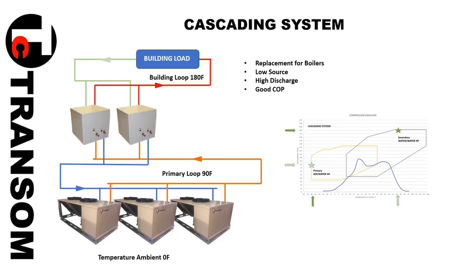Have you experimented with split systems that make it possible to get rid of the heat exchanger and the heat transfer fluid that's antifreeze in your primary loop? Yes, I've done that before. And if it was ground source, you could do it. But with air source, it's such a wide variety of source temperature and the amount that you get out of it. So it's very hard to control the ratio of the primary secondary compressors.